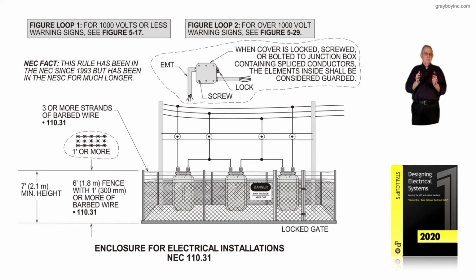exception 1 and follow the rules, and it looks like with that we could have as many mains as we wanted in the switchgear at the facility if there wasn't an ordinance or another area in the code that would override that exception and only allow 6. So keep this in mind, that 110.31 of the NEC is showing 3 barbed wires that would extend a 6-foot fence to a 7-foot fence to guard the energized components of the equipment inside the substation and keep unqualified people from entering that substation and accidentally getting maybe hurt real bad, and in some cases, maybe even killed. So that's what this section is all about, to guard those energized components in accordance with NEC 110.31.